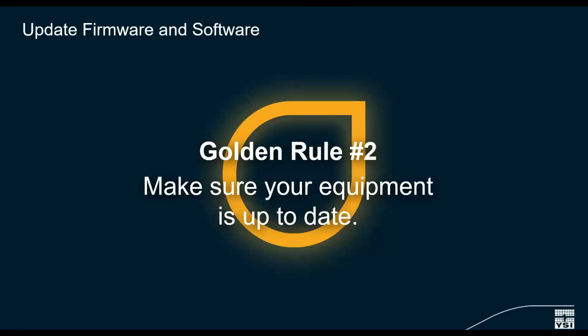So if checking your batteries is the golden rule of tech support, then a close second is making sure your equipment is up to date with firmware and software updates. Golden rule number 2. This is especially the case with EXO and ProDSS instruments, where the instrumentation itself is continuously improved upon by our R&D teams. Chances are, if you are running older versions of software and firmware, any issues you may experience have been resolved in a later update. So before you calibrate sensors or record data, make sure you are up to date so you have the latest features available.